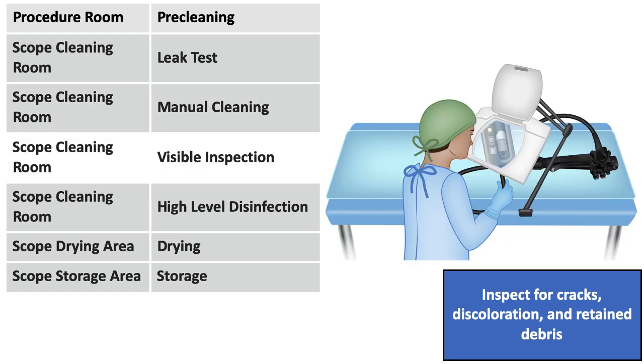Finally, you take time to inspect for cracks, and if there are cracks, you send the scope for repair. You don't put it through the cycle and go back to the next patient. If you see retained debris, you have to go back to the manual cleaning again until you see no debris. These steps, the pre-cleaning, leak test, and manual cleaning, are the most critical things that need to be taken care of by every endoscopy unit.